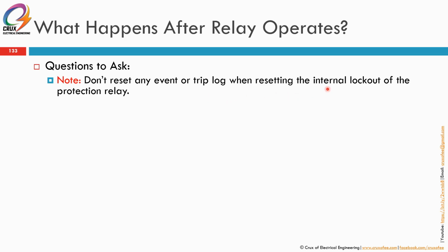Because in some of the modern relays, we are using the internal lockout instead of the physical lockout relay for this. So people might wrongly reset this event or trip log, and this will be a hindrance to us when we want to troubleshoot in terms of finding the actual last cause of trip, what is the last event which occurred prior to the tripping.